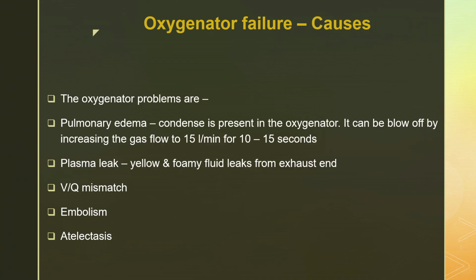Second is plasma leak, which you don't see in the polymethylpentene (PMP) oxygenator, only in the polypropylene oxygenator. Third is ventilation-perfusion mismatch: some area of the oxygenator ventilates well but doesn't perfuse well, or vice versa, similar to what you see in ECMO. You can also have massive embolism going to the oxygenator and blocking it completely, or some gas fibers degenerating into atelectatic fibers that don't do gas exchange.